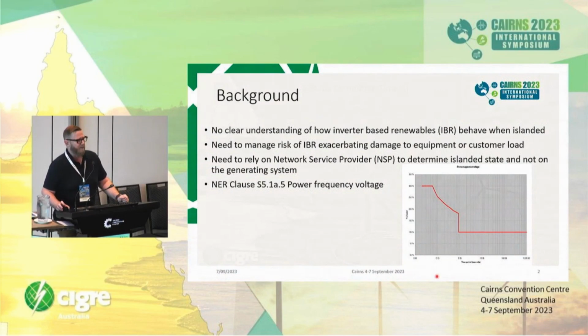So the background is really when we first started, when we were looking to get our first inverter-based renewables online, we had no clear understanding of how they would react or respond when they're part of an island. So we needed to manage the risk of an IBR exacerbating damage to our equipment or customer load. Additionally, the NER clause states that for a credible contingency event, the voltage of supply at a connection point should not rise above its normal voltage by more than a given percentage for a period of time, as per the graph. So overvoltage as well was something that we wanted to account for. Typically it's the responsibility of the generator itself, but we wanted to make sure that we were protecting ourselves there as well.